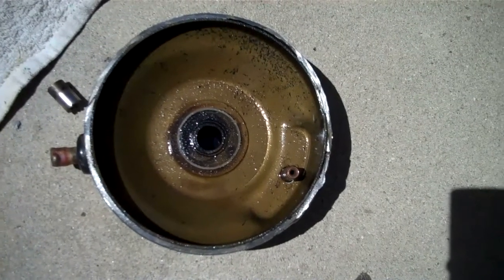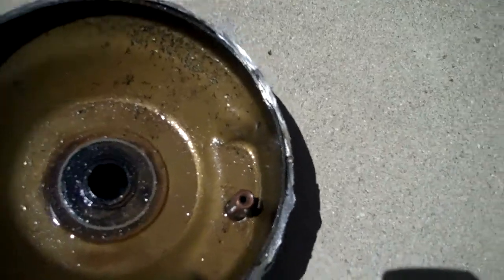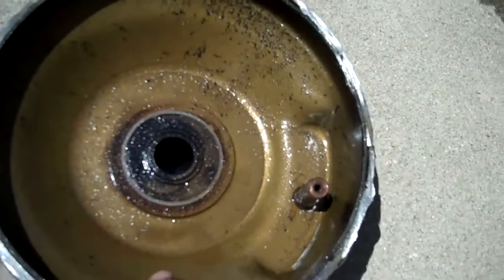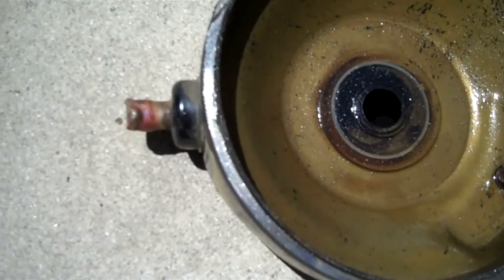This is the top of the compressor. There's the relief valve, the pressure relief valve, then your discharge going out the center and kicking out the side over here.